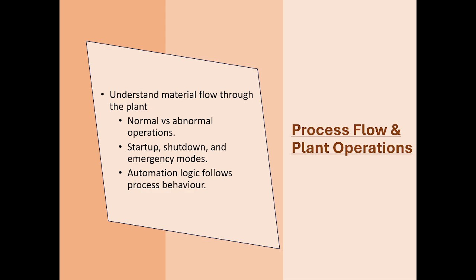Process flow is the story of the plant, and it describes how raw materials enter, move through equipment, and exit as a finished product. Plants do not operate in one steady condition. They have startups, shutdowns, and abnormal situations, so automation logic changes based on these operating modes. When an engineer understands the process flow, they can predict problems even before alarms occur. This now naturally brings us back to safety and protection philosophy.